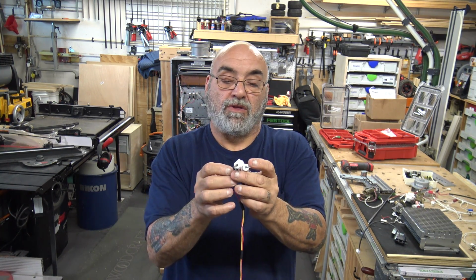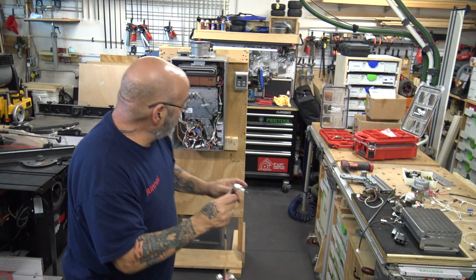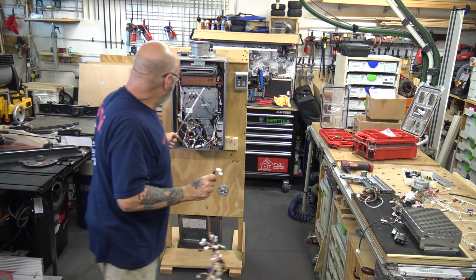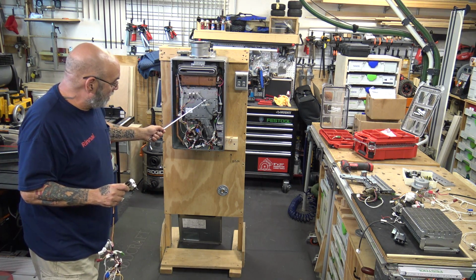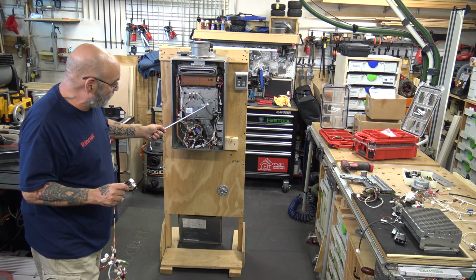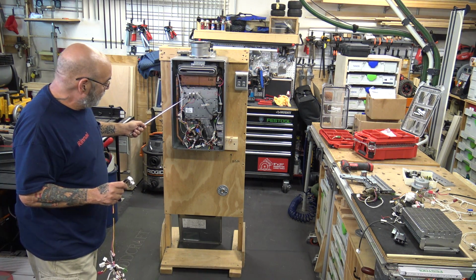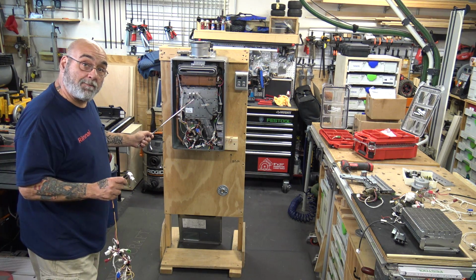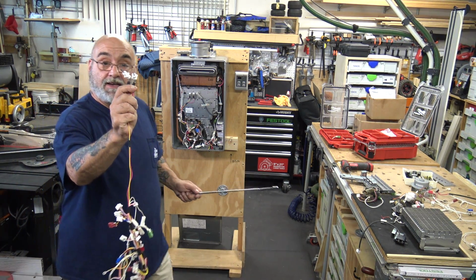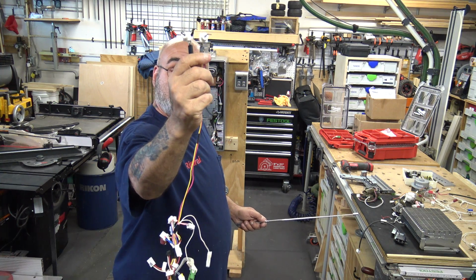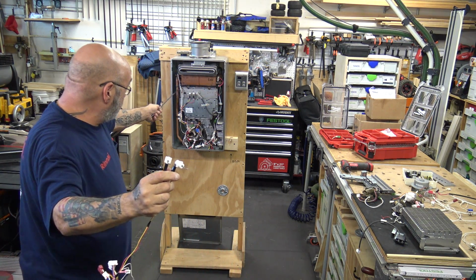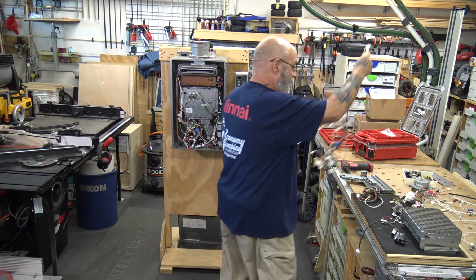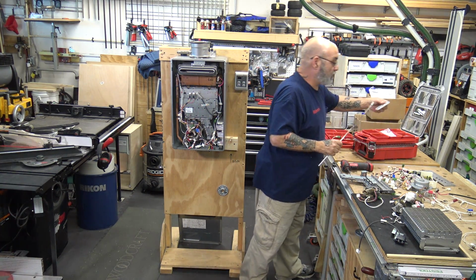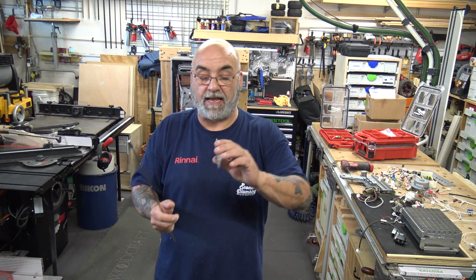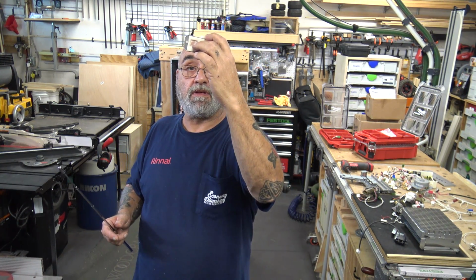Now remember, when they go back in, remember the orientation. The igniter is going like down towards 4 o'clock, 4 and 5 o'clock. The 2 flame sensors, yellow and red, are going down to 6 o'clock. So remember that orientation. So they face, you see how they're going down to 6? So they're facing the left side of the burner. Then you have your burner, then you have your igniter and flame sensor plate with the gasket.